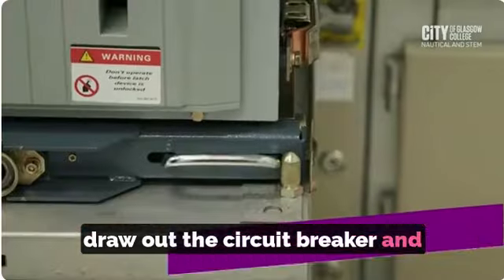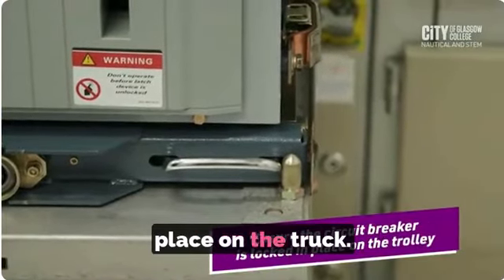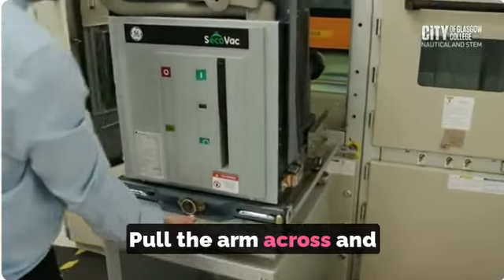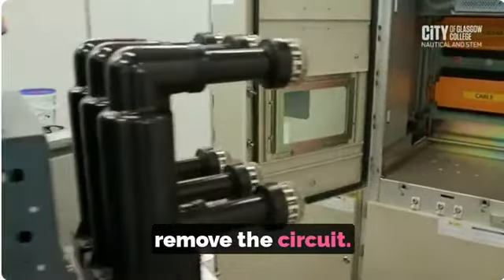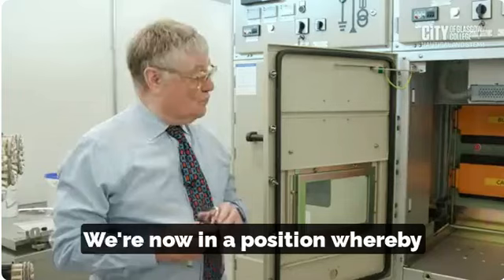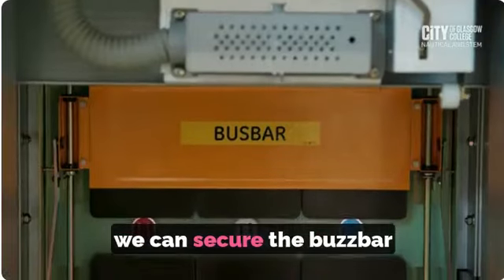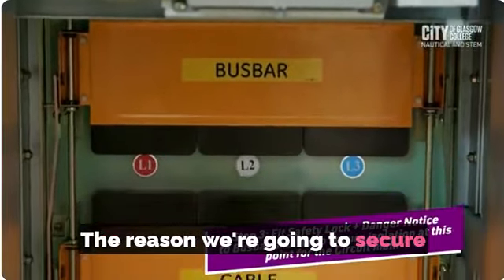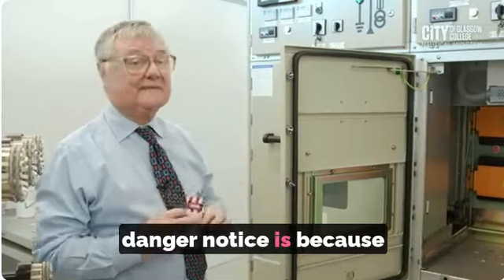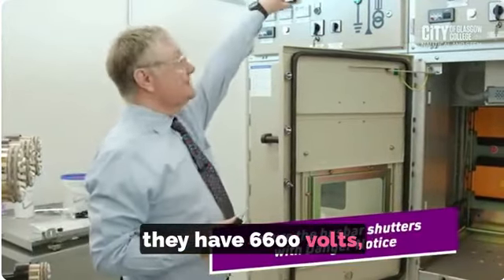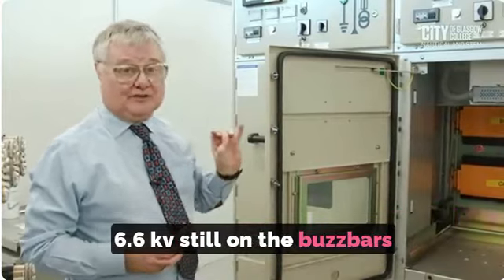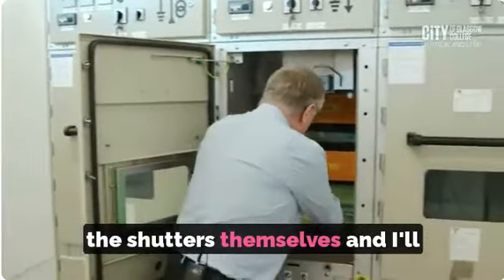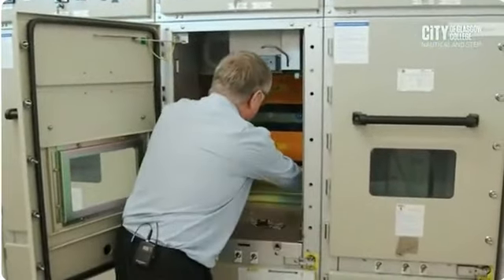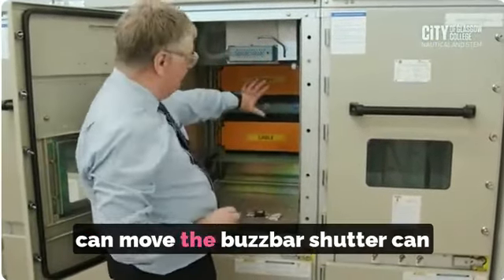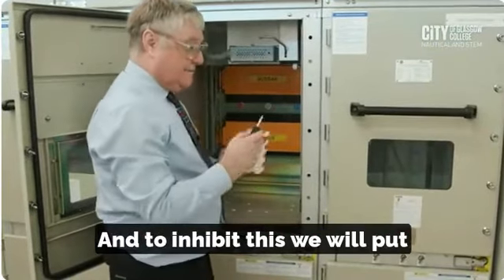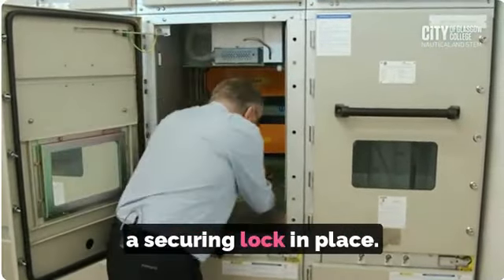Draw out the circuit breaker and make sure it's locked in place on the trolley. Pull the arm across and remove the circuit breaker. That's the circuit breaker out. We're now in a position whereby we can secure the busbar shutters. The reason we're going to secure the busbar shutters with the danger notice is because they have 6,600 volts, 6.6 kV, still on the busbars. The shutters themselves, and I'll demonstrate with the cable shutter, can move. The busbar shutter can move in a similar sort of way, and to inhibit this we will put a securing lock in place.